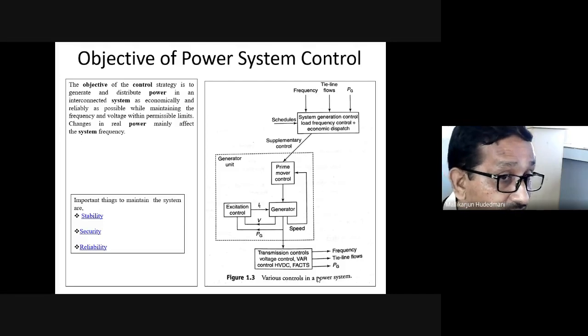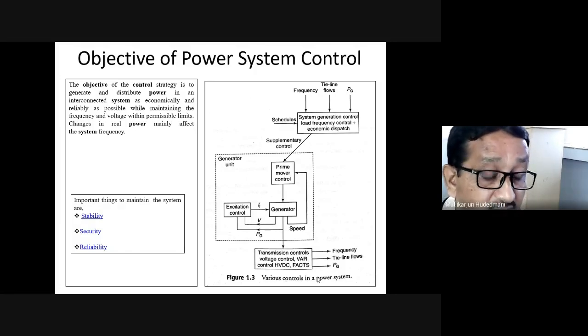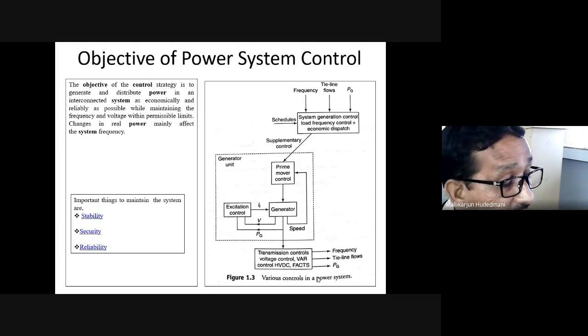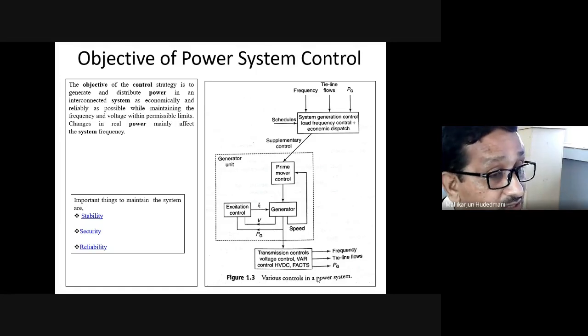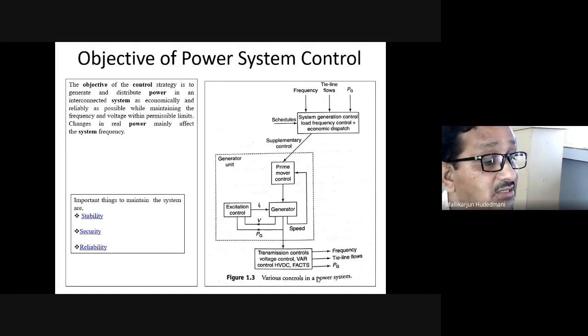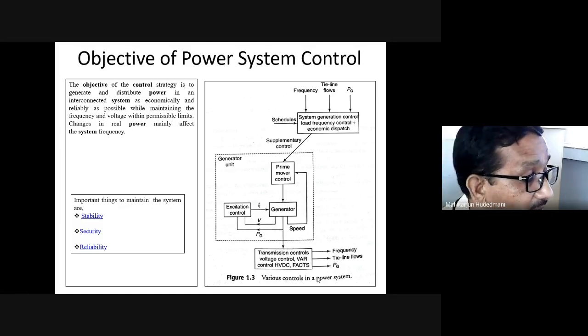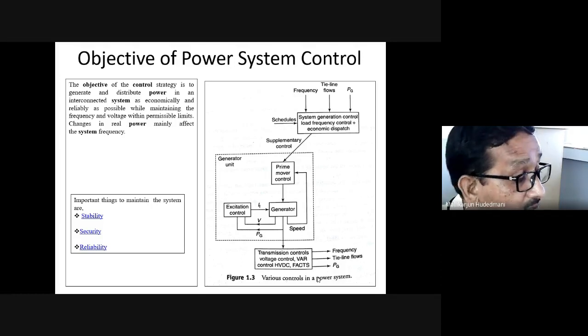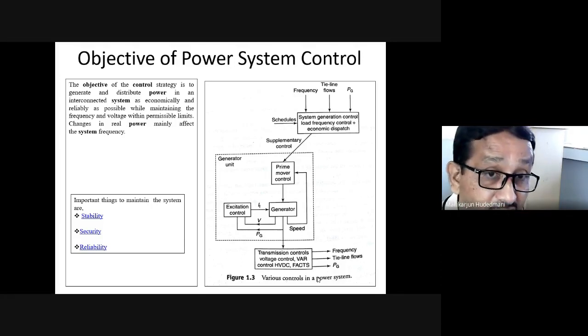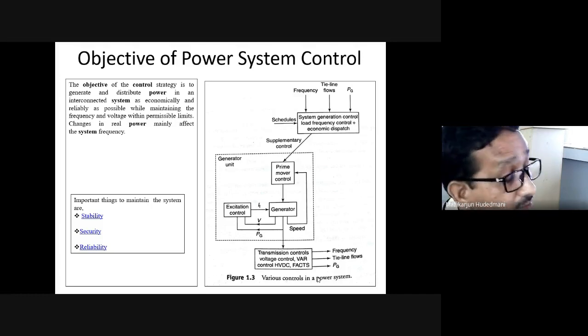The other term, reliability, is a probabilistic approach to understand and evaluate the availability of a certain component, certain generator, certain transmission line to meet the requirement of the end user at a certain time of operation. Will that component be there or not? What is the probability that a certain identified component will not be there for your service? It is called failure. That kind of mathematical evaluation is done in the reliability approach. Again, I propose this is another engineering aspect which must be done without fail.